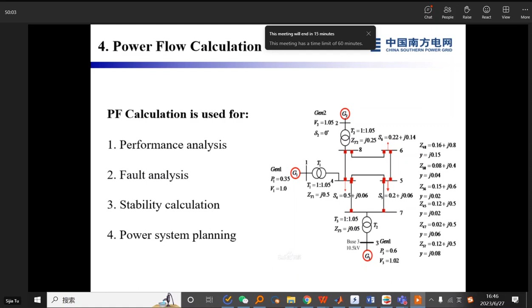So power flow calculation is used for performance analysis, fault analysis, stability calculation, and power system planning. For each bus in the power system, there are 4 variables to determine its operating state. Every node, every bus in the system contains 4 parameters: P, Q, U, theta. P means active injection, active power. Q means reactive power. U means voltage amplitude. Theta means voltage angle, the phase angle.